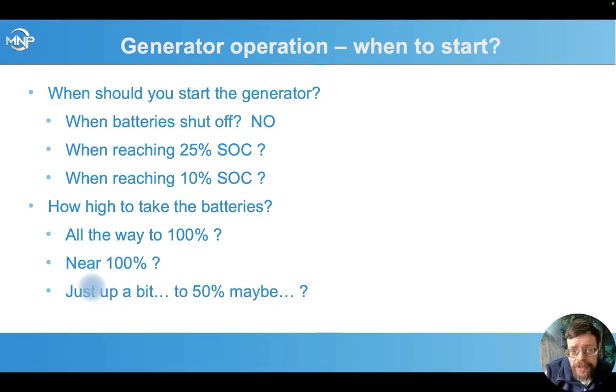When should you start the generator? The common method of doing it was often when the batteries shut off. That's a really bad way to do it. That's like waiting to fill up your car with gas till you run out of fuel on the side of the highway. Oh, I guess I should fuel up now. But now it's really obnoxious. With lead acid batteries, that was damaging the batteries. With lithium batteries, by the time the batteries shut off, they'll actually shut off before they damage themselves, but often that requires a manual restart of the batteries when they shut off, so it's really not the best operational procedure.